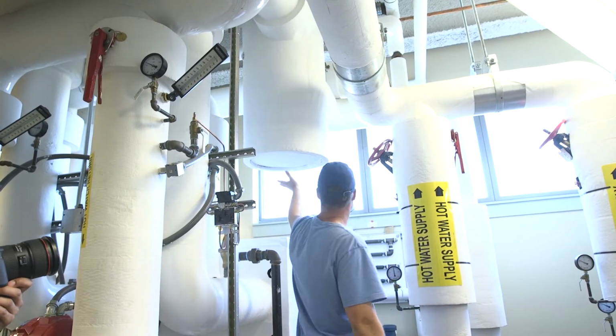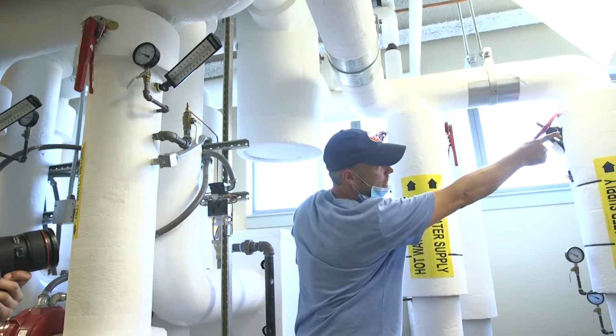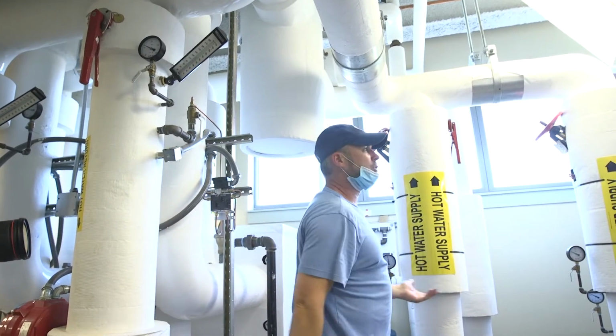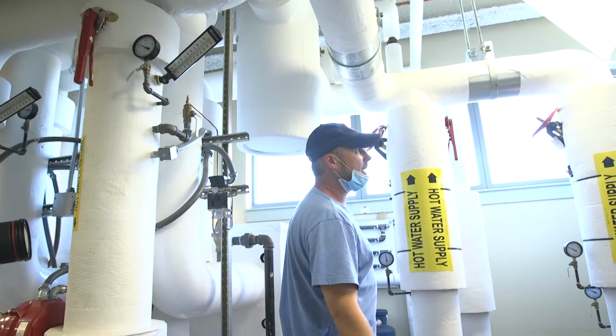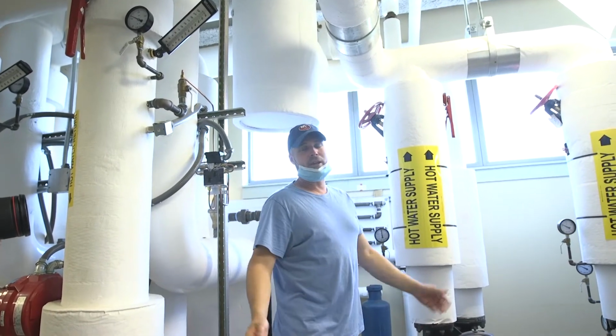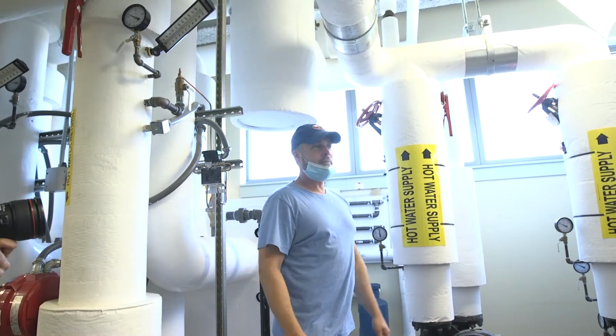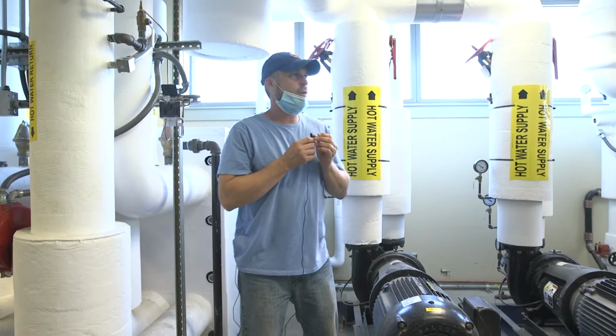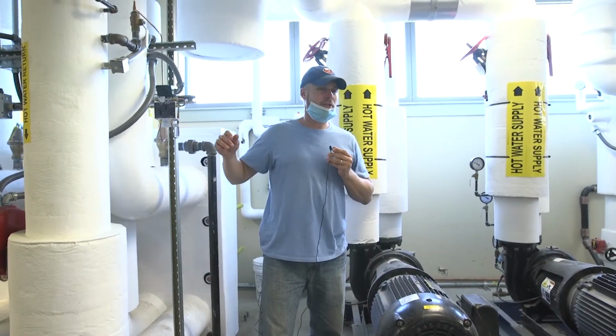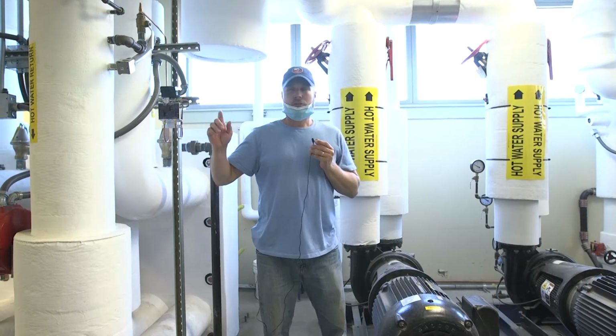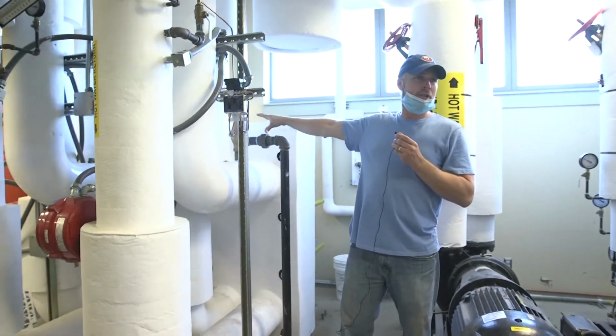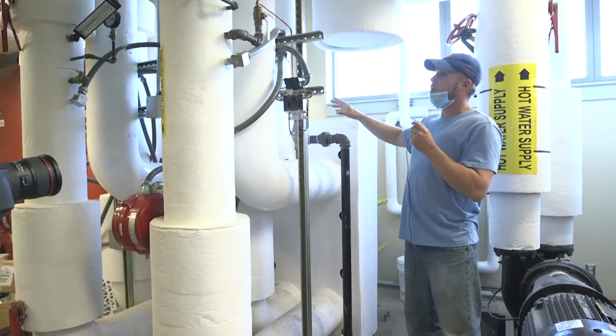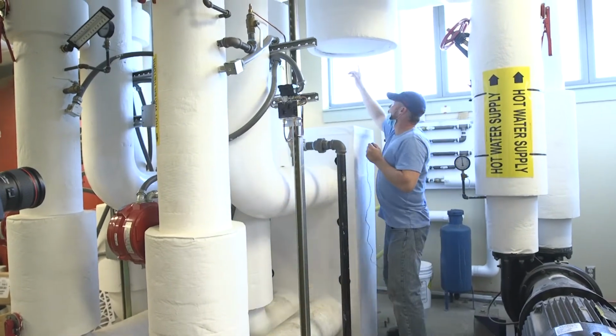You've got a blow down strainer. You can pull this head off. That one's a little exposed. You can blow the schmeg out of the bottom of it, a little dirt leg. That should be done very rarely. Once a year maybe. The one last thing I wanted to mention is the bypasses. So around each one of these heat exchangers, they installed a bypass.